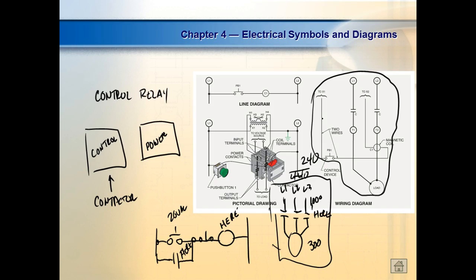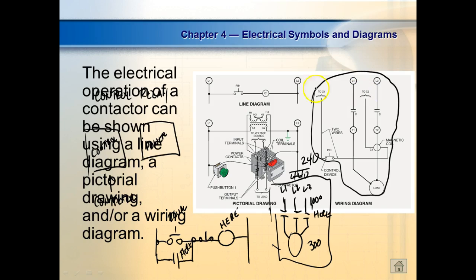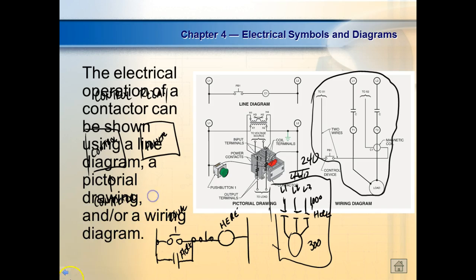That's why when you look at that HVAC system, it's got the control circuit in there, the one I had before, and it's really hard to trace. So if you've ever worked on an air conditioner, most of the time now when you pop the cover off that covers up all your controls and you flip it around, it's going to have two diagrams on there. It's going to have a wiring diagram, and it's going to have a ladder diagram. Thank goodness. So most control systems consist of a power section and a control section, right? That makes sense? Okay, guys, y'all take another 10-minute break.